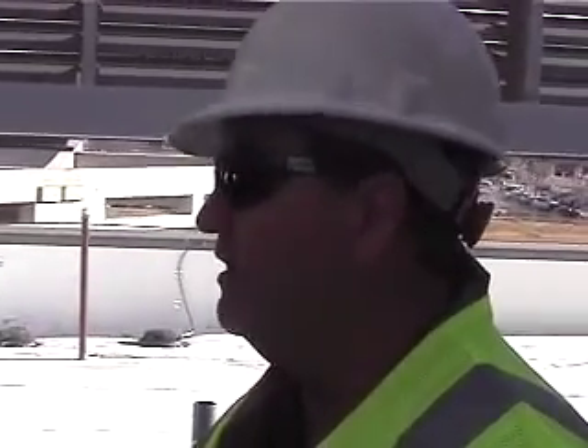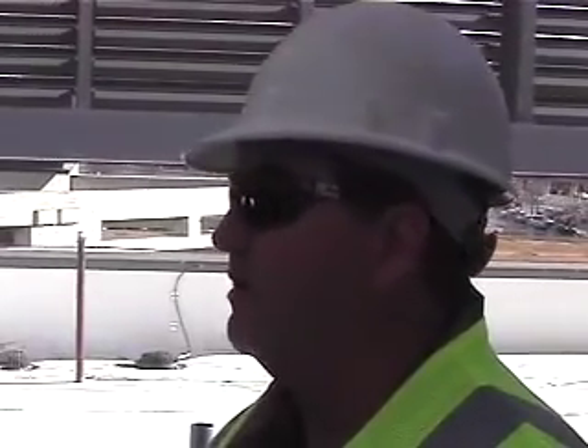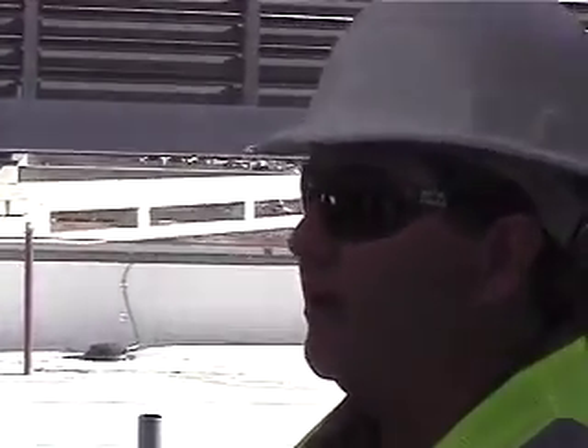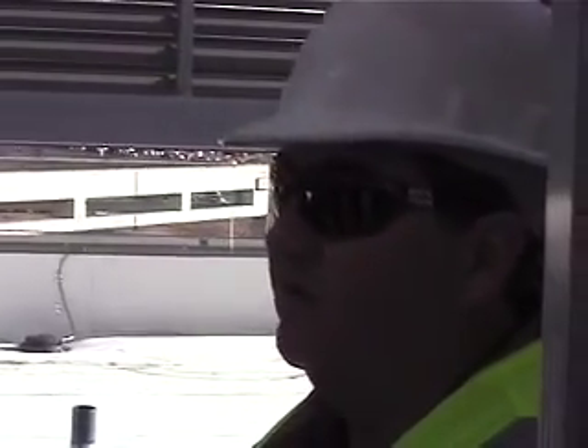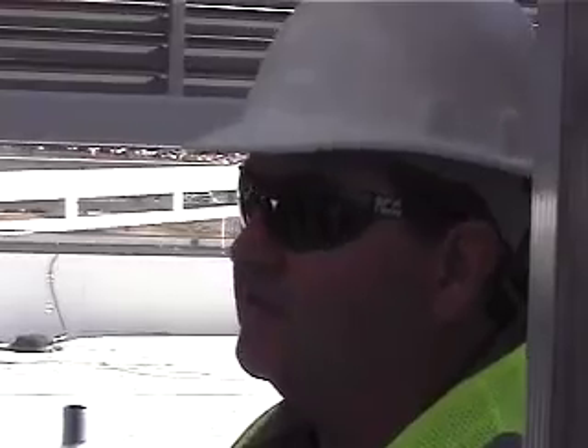Of course, anytime you work on anything, you lock and tag it out. And I would suggest, I always use my own lock. I brought my own personal lock so that no one else could take it off and start it up, because the fan could do some damage. And that is true. Just because the fan's not moving, or just because you shut it off at the VFD, doesn't mean you necessarily got the right fan motor. It could be easy to go in the building, get the wrong one, come out here, and think you have this one locked out, when it's best just to come over and turn it off right there at the disconnect, put your lock on it, and then there's no chance that you made a mistake, or somebody made a mistake and said, yeah, I shut off one.